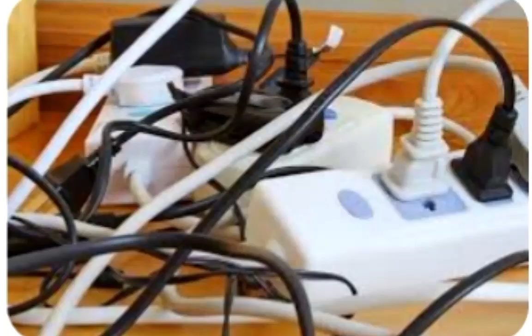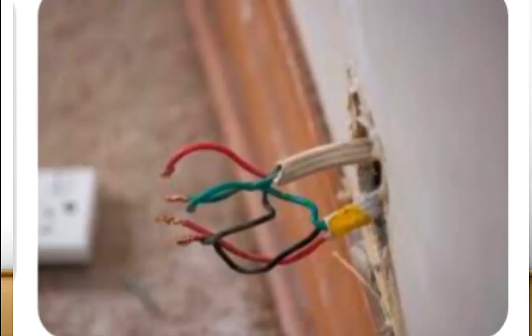First, faulty electrical wiring or connection. Faulty wiring shows some noticeable signs. For example, dimming or flickering lights are signs of bad wiring. Plus, if you experience frequent blown breakers or fuses, there's a good chance that faulty wiring may be to blame. Other common symptoms of faulty wiring include charred or darkened outlets and switches.